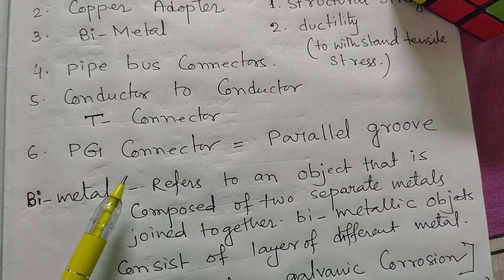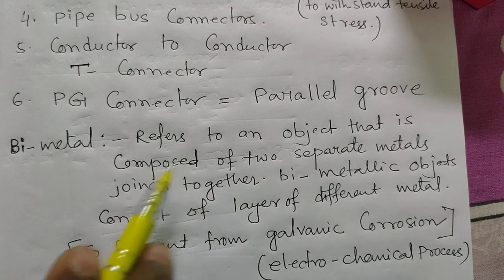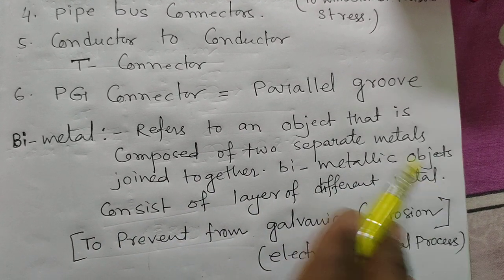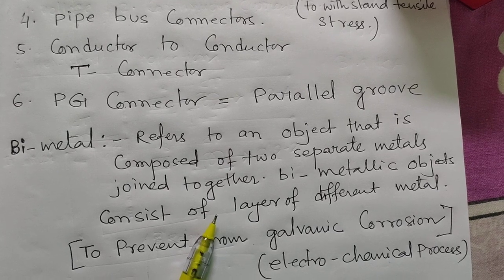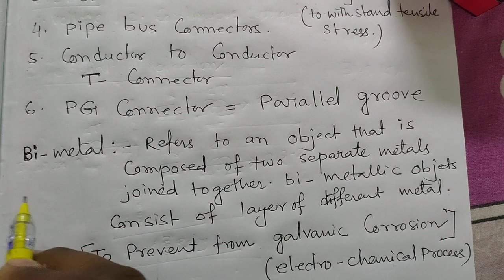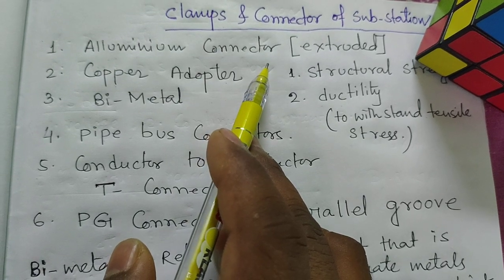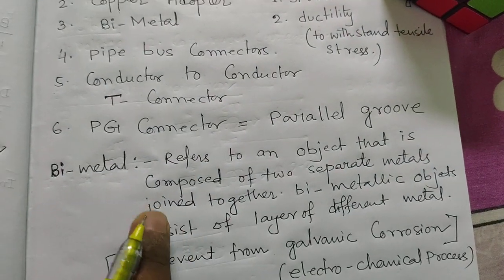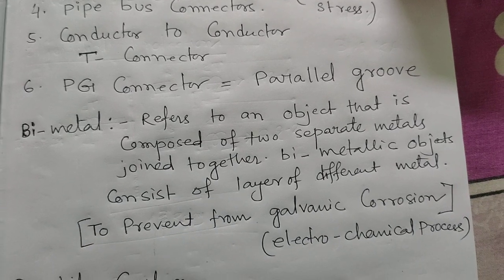What is bimetal? Bimetal refers to an object composed of two separate metals joined together. A bimetallic object consists of layers of different metals — not mixtures, but layers of the two metals. At substations, we use bimetals between a copper contact and an aluminium connector, because aluminium connectors are used for cost reduction, durability, and heat absorbing capacity.